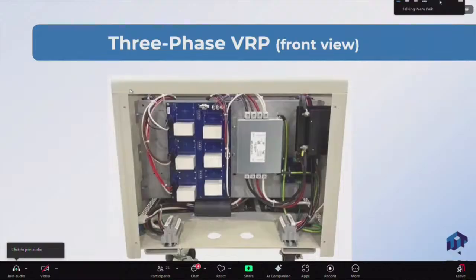So when you open the cover of a three-phase VRP, you will see this facing you. On the left side, you'll see the two bottom holes. These are the cable wire entry holes. Bring in the wire here and make the connections. In case of three-phase voltage, you'll need to bring in 5 wires: phase 1, 2, 3, neutral, and earth ground. You make the connections here, and then you bring in the wires from your load equipment. It could be computers, it could be a CNC machine or telecom rectifier and air conditioners, etc. You'll bring in the wires here and make the same 5-wire connections.